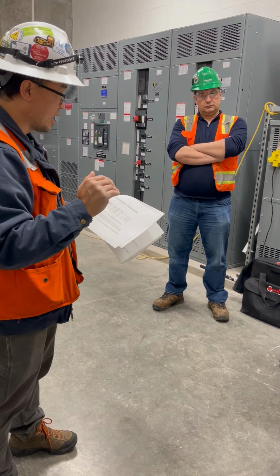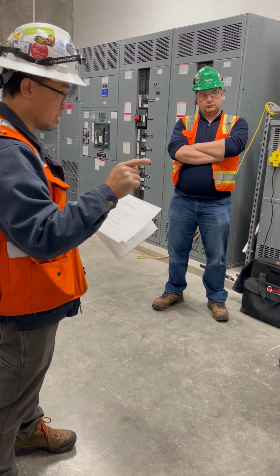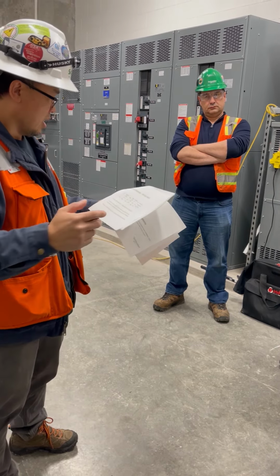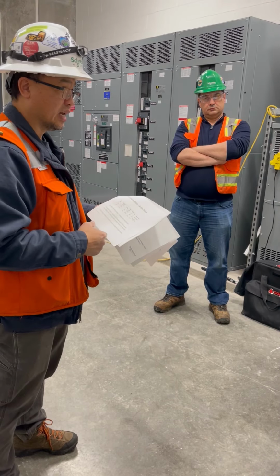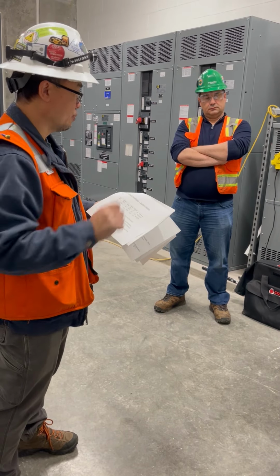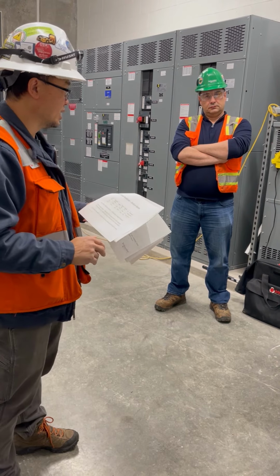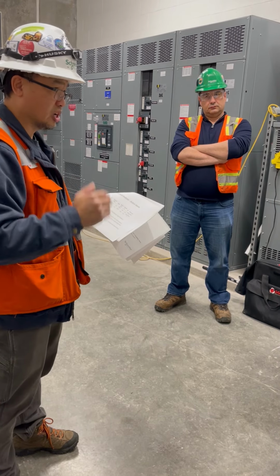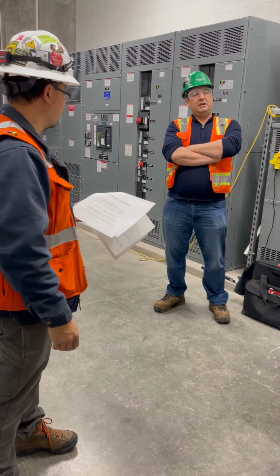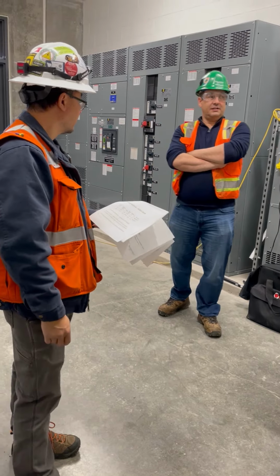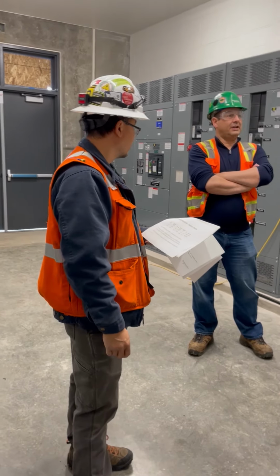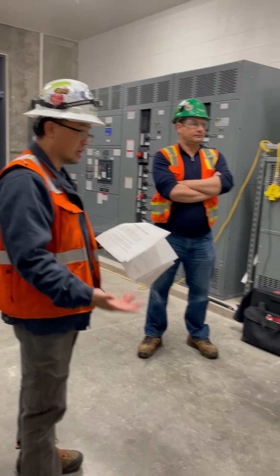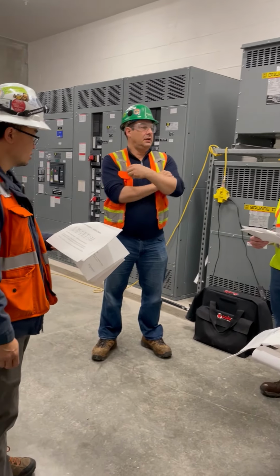So if that panel board is rated for 35K and he decides it's cheaper, let's go with the 18K circuit breakers, he puts those in there, now that panel is rated only 18K, so that whole panel is underrated. And what that means, if a device is underrated, in case there's a short circuit, that device can actually blow up. Because it cannot handle that whole pressure.